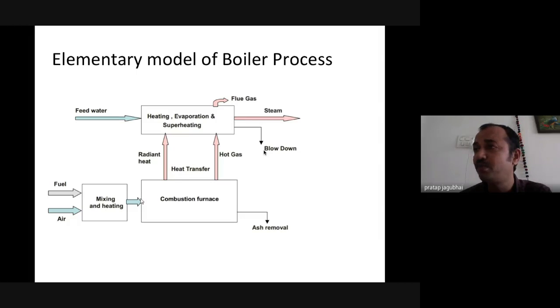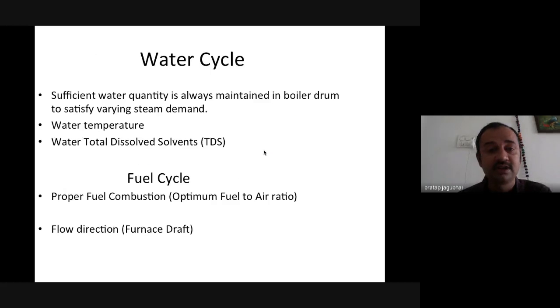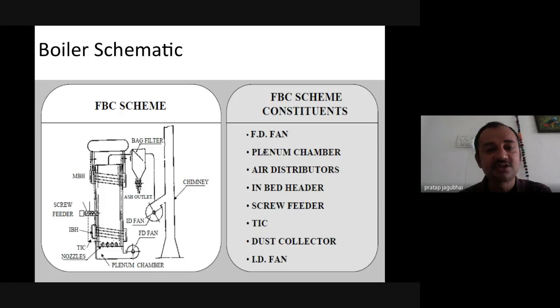That can also be improvised, because more blowdown is more heat loss, and less blowdown means harder TDS level is getting settled inside the tubes, so more heat transfer needs to take place and more fuel needs to be burned. So that is again the heat loss. Now, if we go into more detail of both the cycles, I would like to give the more constructive nature of the boiler.